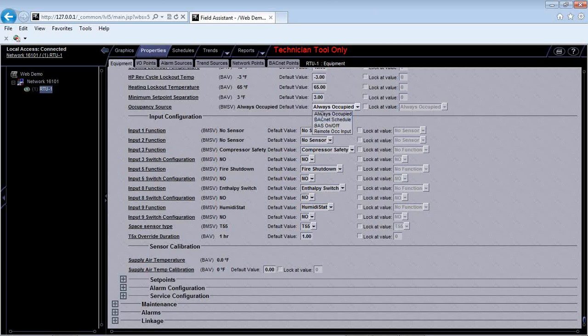So we've got Always Occupied 365 days a year. We have Bacnet Schedule, where it runs off the schedule that I can put on it in Field Assistant or the schedule that a Bacnet third-party control system can write to it. The third option is BAS on-off. This is a lot easier to use with a third-party control system. It's just a Bacnet point or Modbus or LON point that the building controls contractor can write an on value to through the network, and the unit will go occupied. So this allows your building automation system to do their own schedule on their side. Whenever they go schedule, they can just write to this point and turn the unit on or off. Whereas with the Bacnet schedule, they'd actually have to write Tuesday you're occupied from 7 to 10, Wednesday you're occupied from this to this. So this is a little simpler and cleaner for the building automation system.